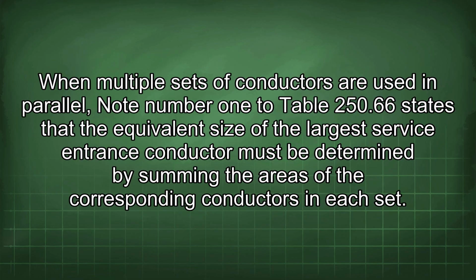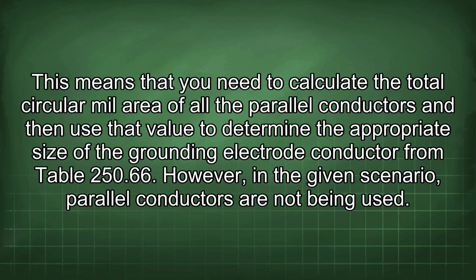When multiple sets of conductors are used in parallel, note number 1 to Table 250.66 states that the equivalent size of the largest service entrance conductor must be determined by summing the areas of the corresponding conductors in each set. This means that you need to calculate the total circular mil area of all the parallel conductors and then use that value to determine the appropriate size of the grounding electrode conductor from Table 250.66. However, in the given scenario, parallel conductors are not being used.